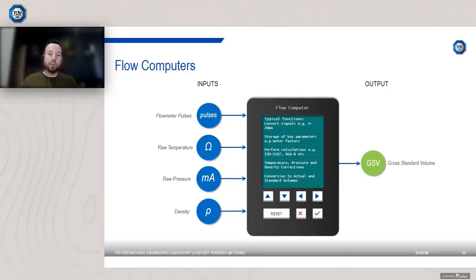So if you've got 4 to 20 milliamp for your pressure, it will convert that into a pressure measurement for you. It will store key parameters like meter factors from your proofs. It'll perform various calculations. So for example, ISO 5167 discharge coefficient or AGA8, natural gas calculations. The flow computer typically is going to do that for you. And more importantly, it's going to convert actual to standard volume.